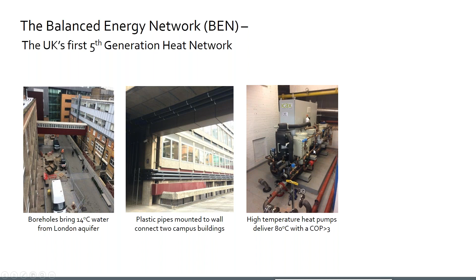A very interesting thing about this, still unique among heat pump and heat network design, is integrating every single component of the network into a demand response addressable control system. Usually when we think about demand response, we link it to specific individual assets like a car battery or a standby generator. What this did was integrate across every electrical component in the network and the heating control system itself - so we're flexing not just the electrical loads of the heat pump, circulation pump, and storage tanks, but also the actual temperature of the building, the thermal mass of the building itself.